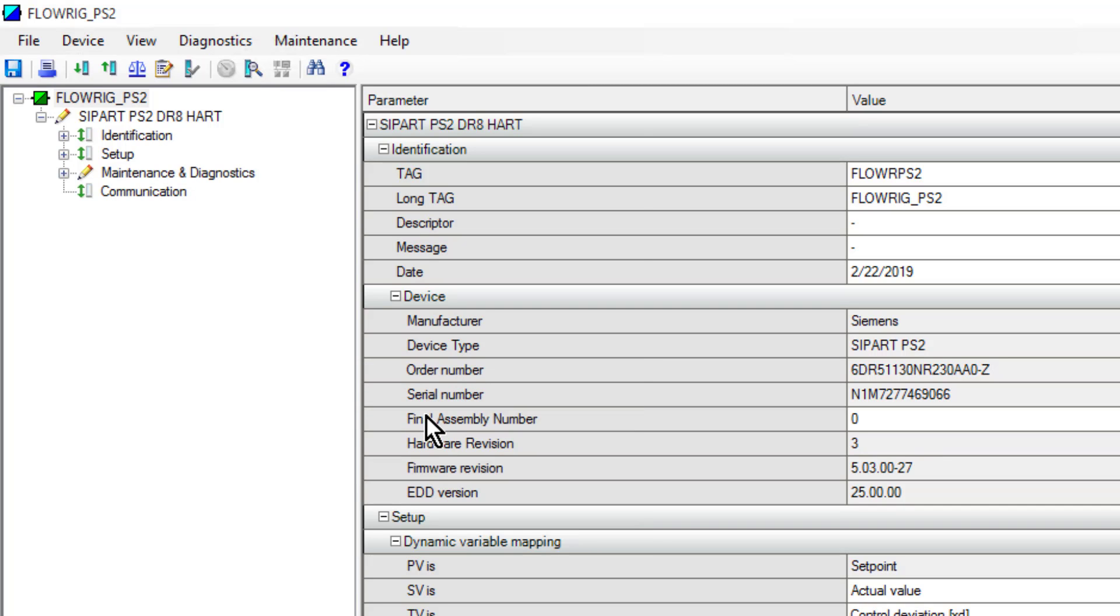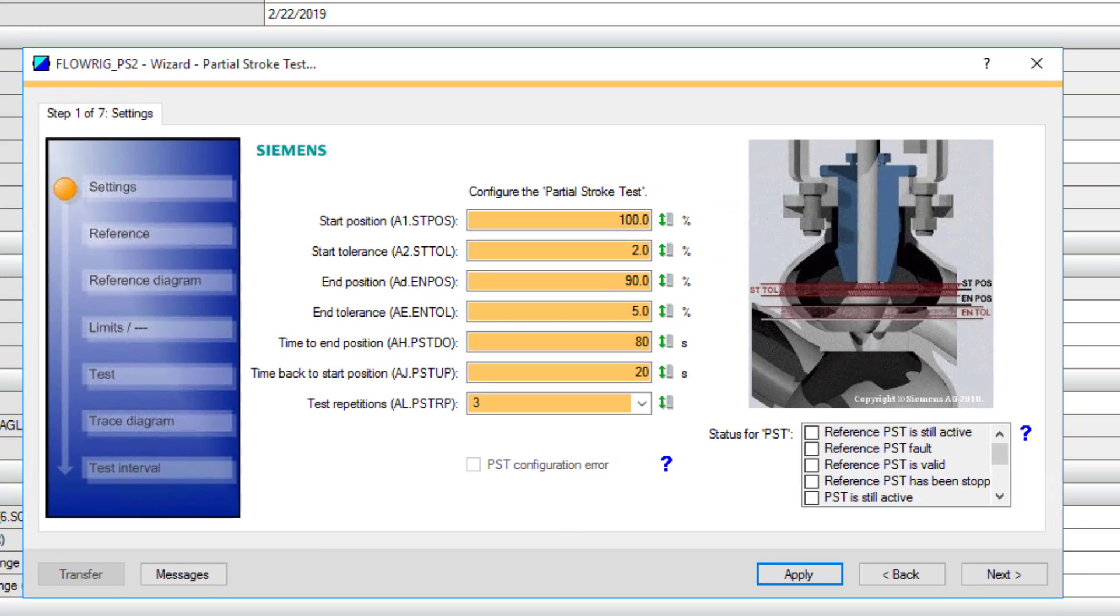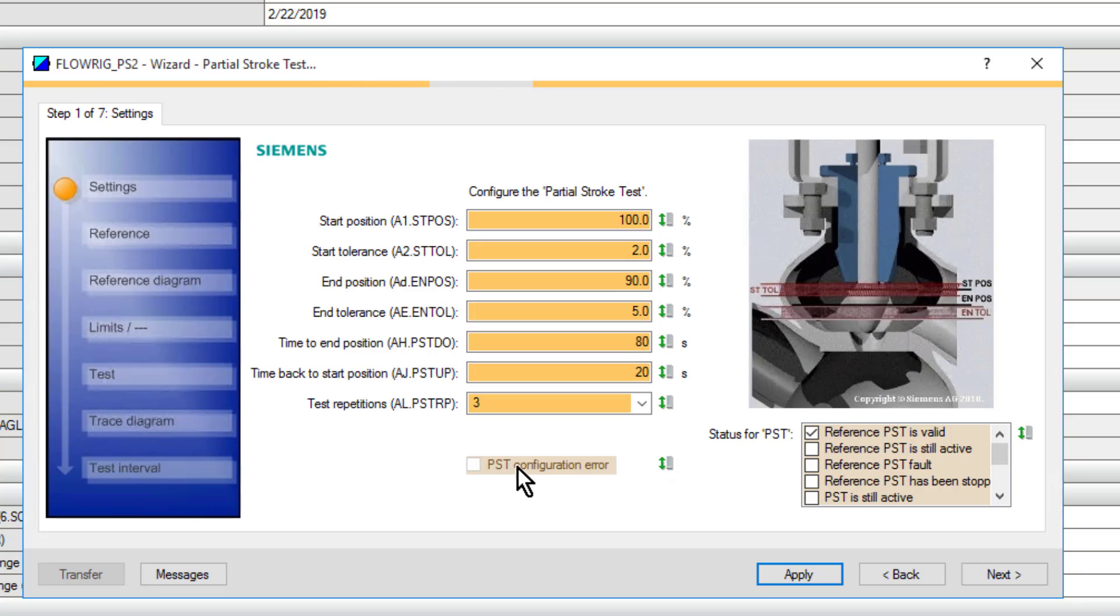We've had the partial stroke test on the PS2 for a long while now, but we haven't had this advanced functionality with the built-in pressure transmitters. This is my setup screen. I'll get an error here if I program any of these wrong. We have to have the valve at 100% open in my case with a tolerance of 2%. That's its start position.